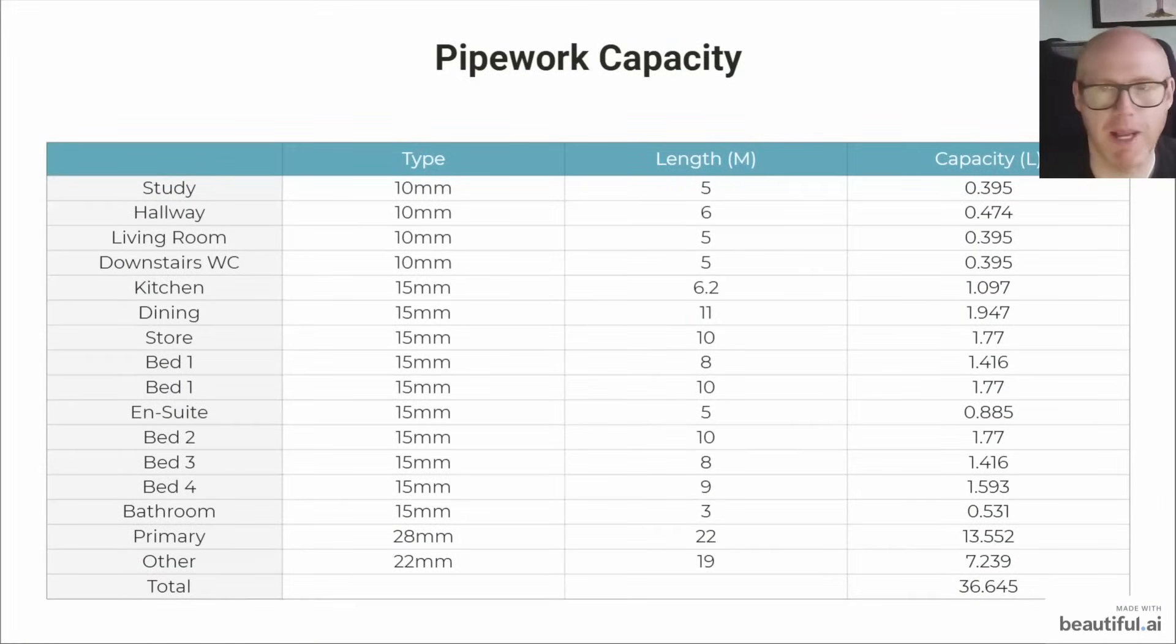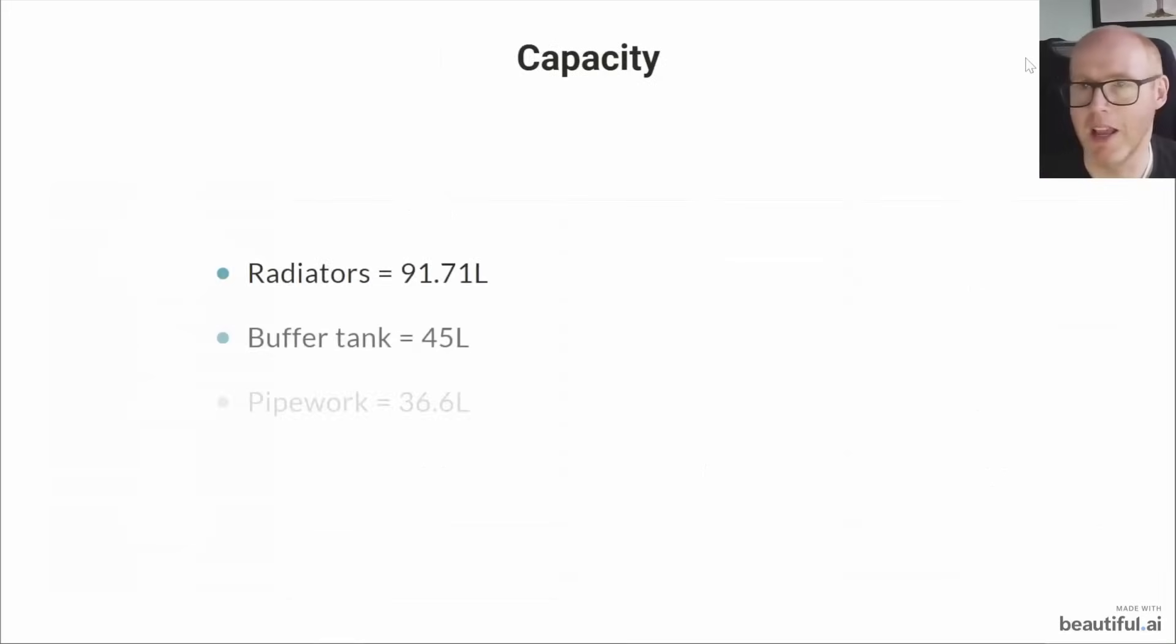Here's my pipework capacity. Once again these are all the radiators here, this is the pipework that runs to them, that's how long the pipework is, and then that equates to how much capacity there is. You can see my primary runs is 13 and a half litres in the 28 mil primary pipework, and that one was super easy to measure so I know it's very accurate. Some of these other ones I've erred on the side of caution, so this is a conservative estimate of 36.645 litres of water capacity in my pipework.